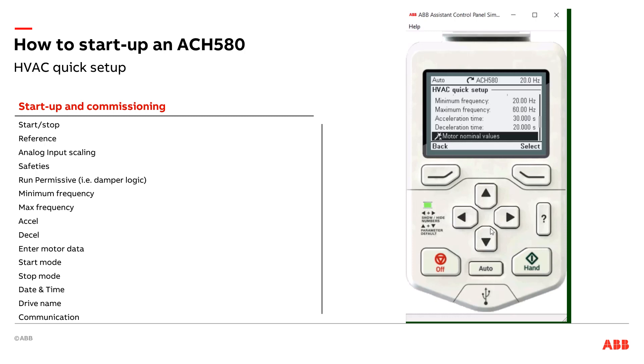Motor nominal values — this is where I'd go in and enter my motor nameplate data: what is my RPM, what is my amps, what are my horsepower. Fun fact: factory defaults are configured for the Baldor Super E motors. So if you left everything at default and forgot to set this and you had those Baldor Super E's, the drive's already set up appropriately. But it's always a good habit to go in there and set your motor data.